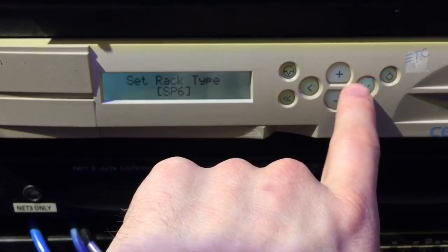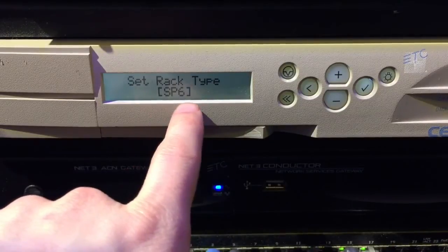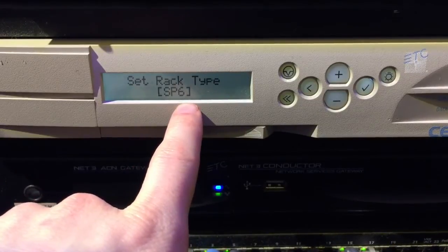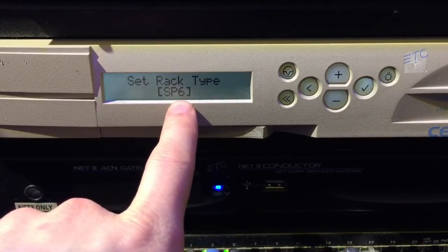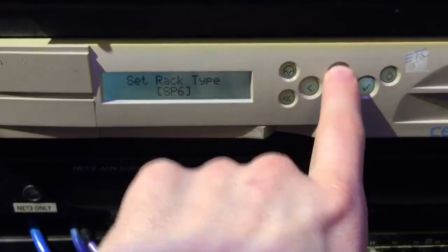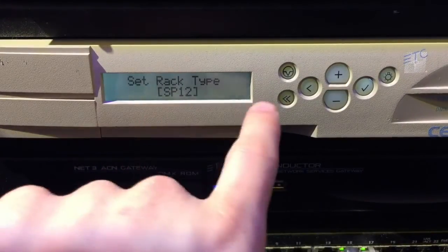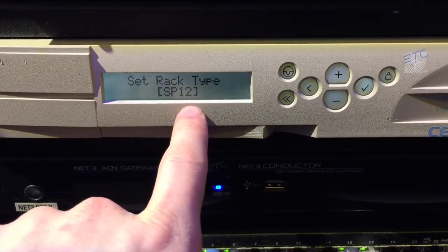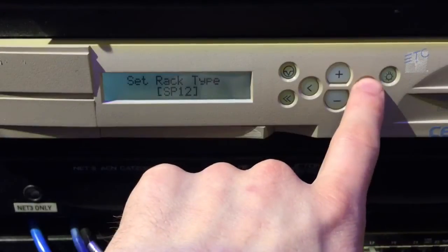Then set rack type. SP6 stands for sensor portable six, where six refers to the number of modules, not the number of circuits — so that's six modules and 12 circuits. We're going to go up to what most people have, and that's an SP12, which is 24 circuits. It does go all the way up to 48, so you can do the large touring racks with 96 circuits. Go ahead and press check mark.